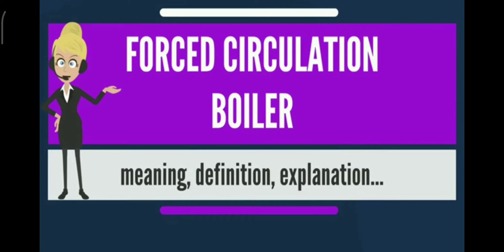What makes the forced circulation boiler different is its use of a secondary pump that circulates water through the boiler. The secondary pump takes the feed water going to the boiler and raises the pressure of the water going in. In a natural circulation boiler, the circulation of water is dependent on the differential pressures caused by the change of density in the water as it is heated. In contrast, the forced circulation boiler uses a water circulation pump to force that flow instead of waiting for the differential to form.